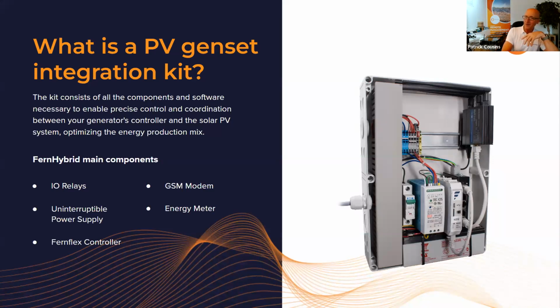Near the top you can see a kind of a big gap. Usually that would be full with various digital analog sensor devices, maybe an energy meter. But of course there are systems that don't need one energy meter, they might need 8 energy meters, and that's possible too, it just wouldn't sit inside this box. So really what we're doing is communicating between the generator, the grid status, the loads, and the PV in order to reduce as best as possible the amount of runtime the diesel generator needs to have.